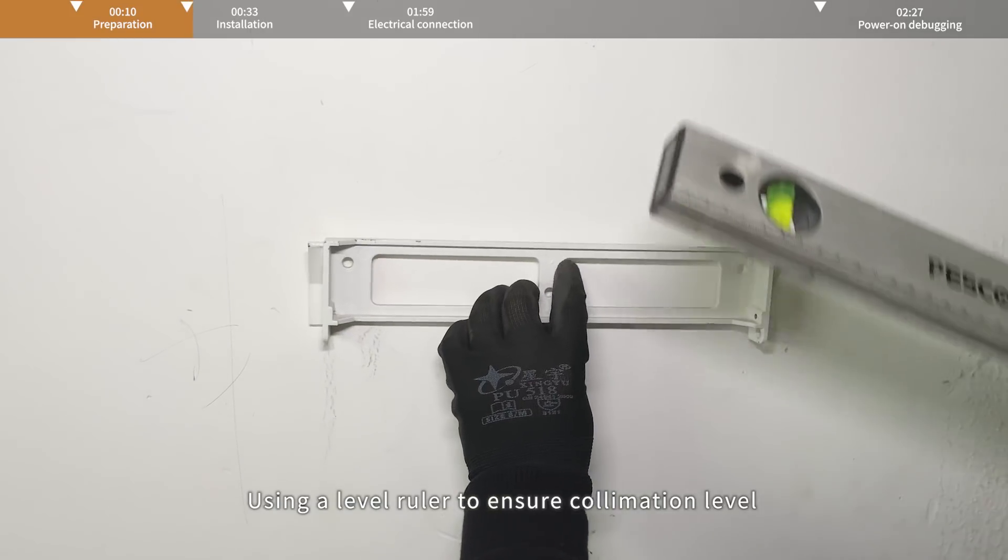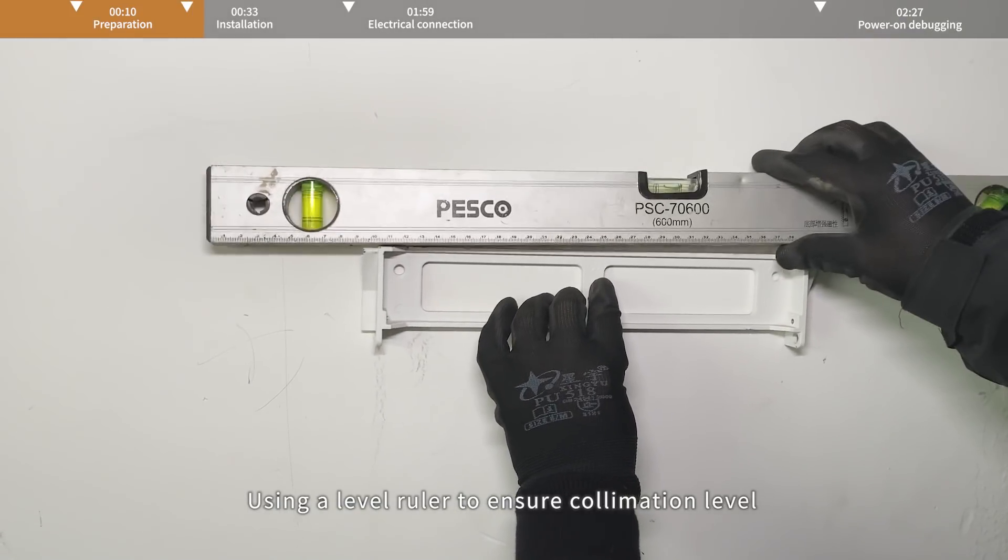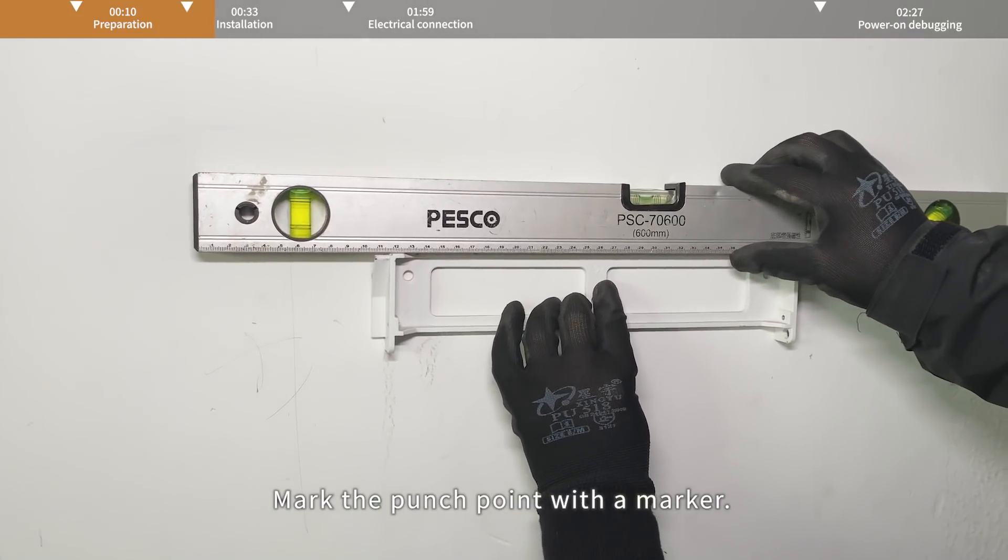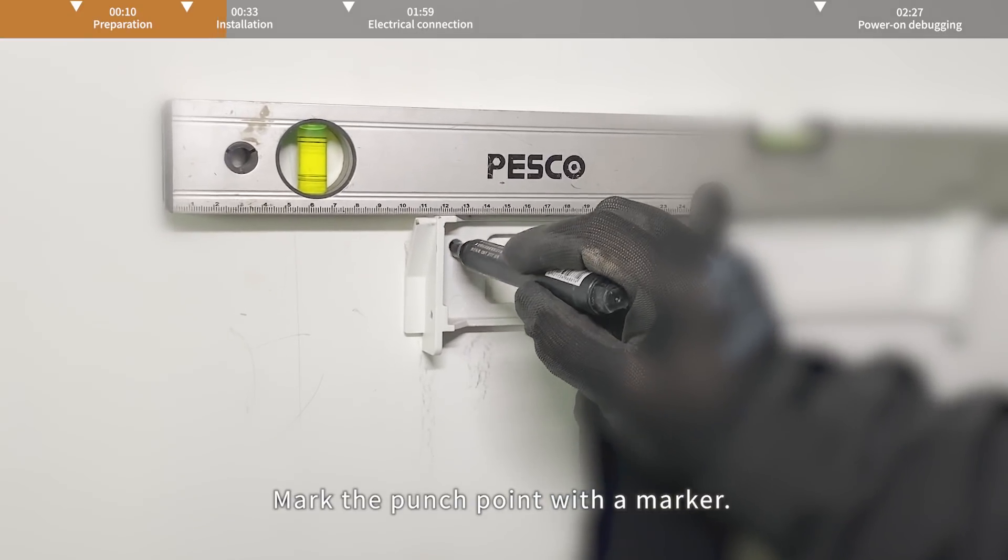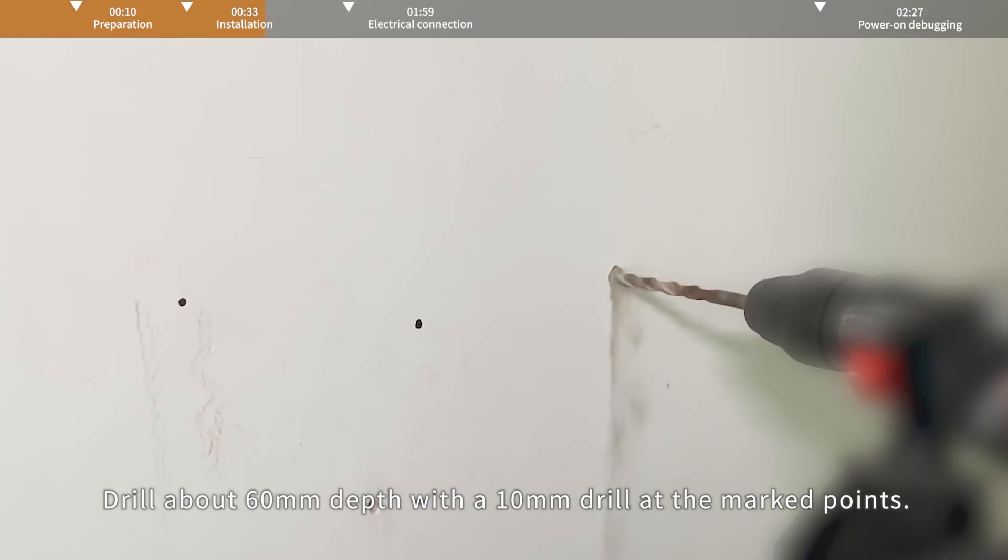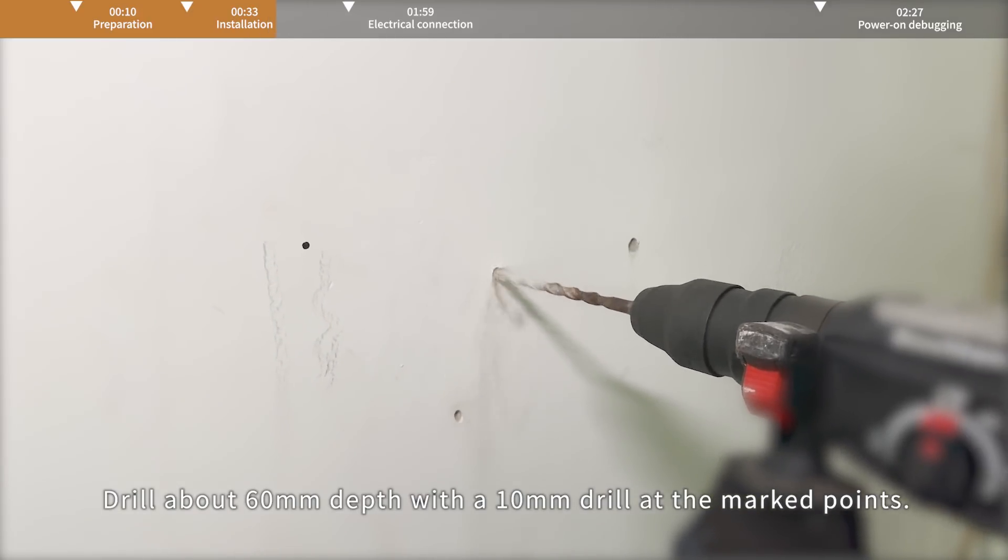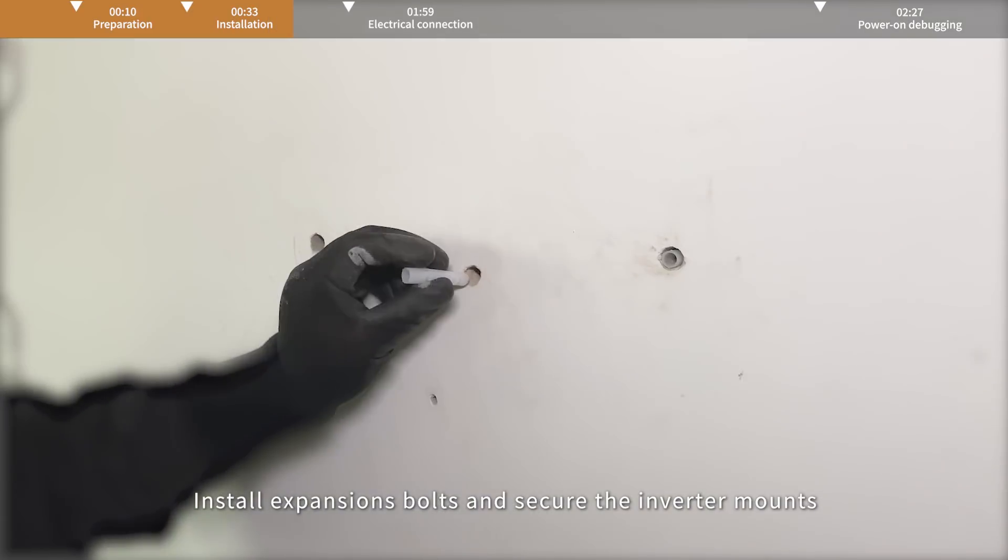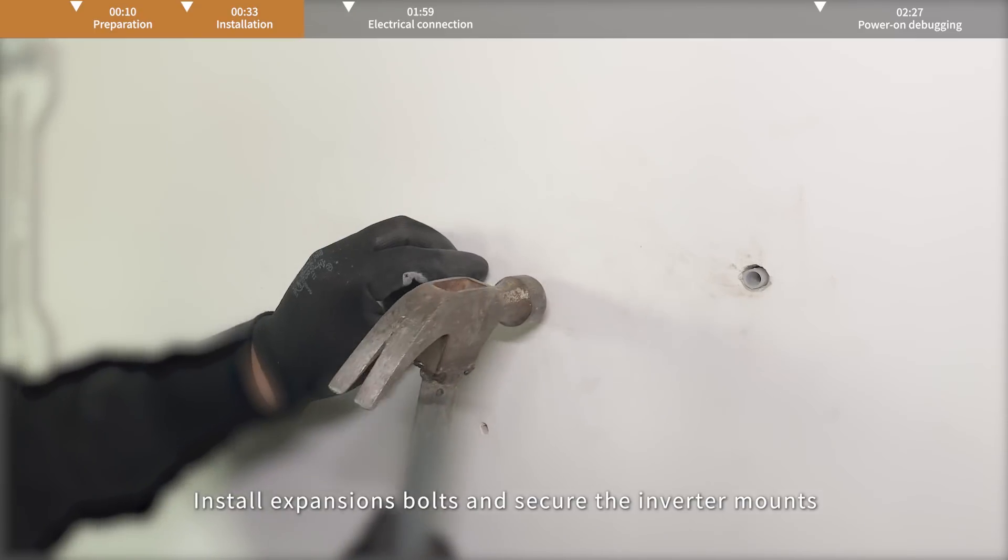Using a level ruler to ensure collimation level, mark the punch point with a marker. Drill about 60mm depth with a 10mm drill at the marked points. Install expansion bolts and secure the inverter mounts.